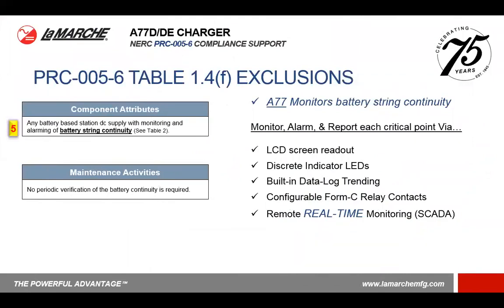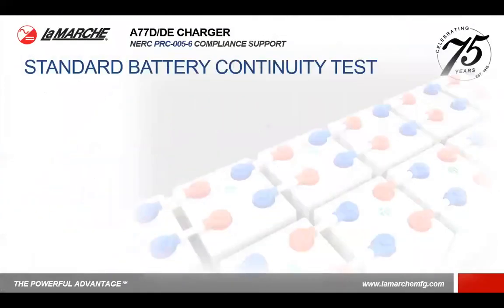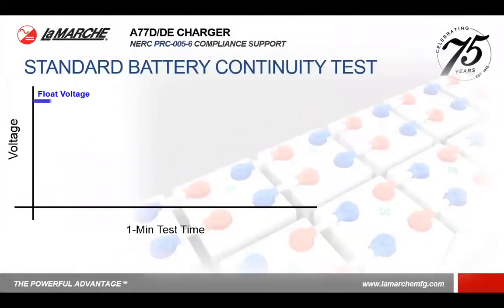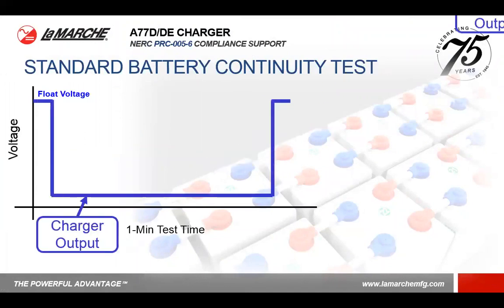Next on the exclusions table is battery string continuity, point number 5. Well, the A77 already monitors for battery string continuity. We'll start out with the float voltage, and we'll apply a 1-minute test where the charger output drops to a lower yet safe operating voltage. This is above the end of discharge voltage on a typical battery system.